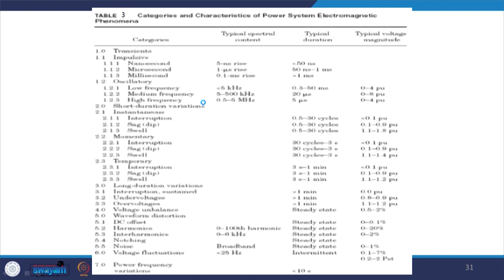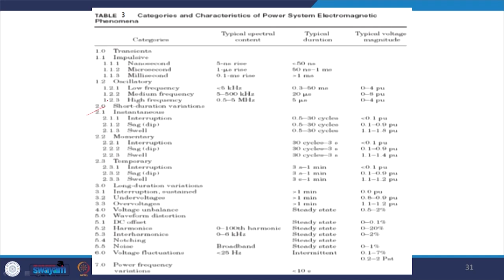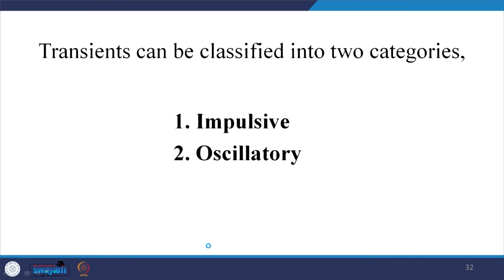This is the categorized characteristics of power system electromagnetic phenomena. It has been discussed in detail in a separate standards class, so only selected values are highlighted here. For example, interruptions last 0.5 to 30 cycles at less than 0.1 per unit; impulse durations can be in microseconds or milliseconds; sag, swell, DC offset, harmonics, and bandwidth are all tabulated. Transients can be classified into two categories: impulsive and oscillatory.